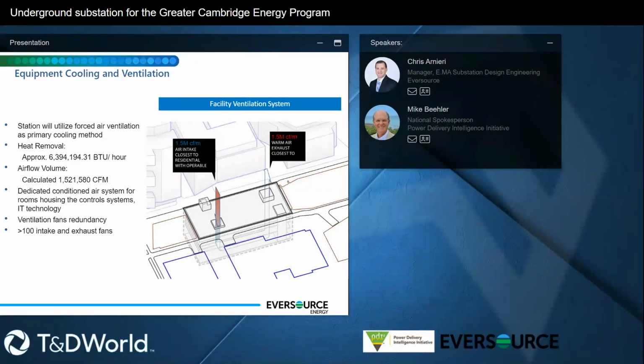Another big thing we had to look at is how do we cool and vent this whole thing. When you look at just the transformers and the residual loads from the switchgear and everything else, and the fact that thermally you're surrounded by a blanket by being this far below grade, our calculations came to somewhere around 6.3 million BTU per hour for heat removal. That translates to about 1.5 million cubic feet per minute of airflow required to keep this at operational levels for all the manufacturing plus personnel.